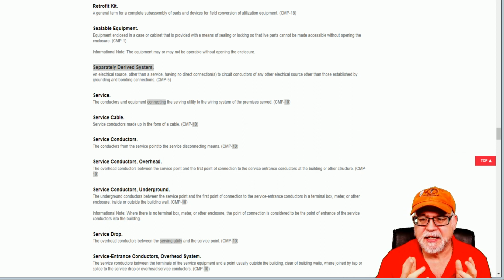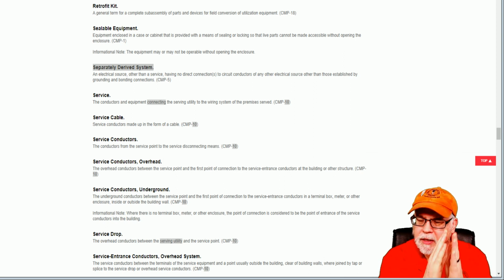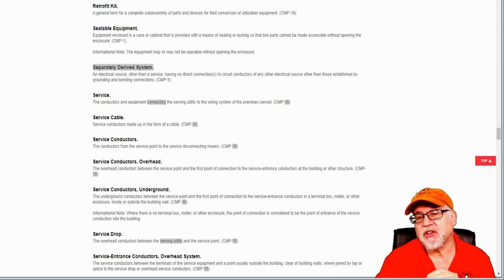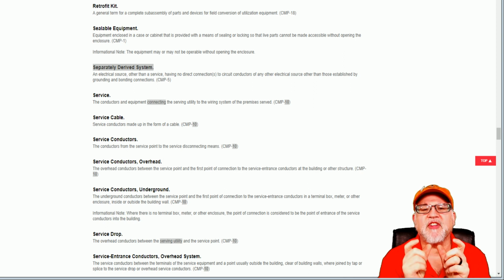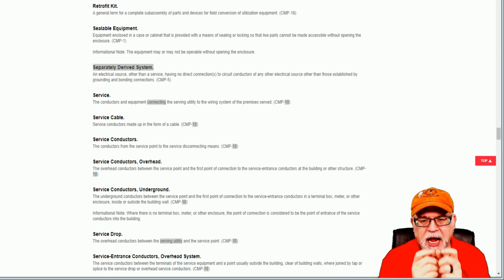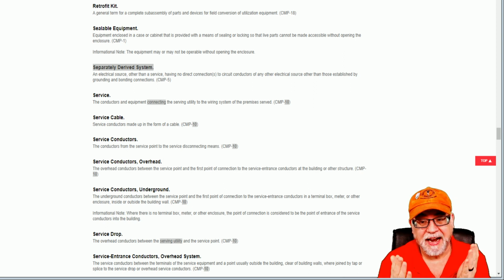Now, we still have bonding. We still have all those requirements that will be intimate. We're talking about the ungrounded and grounding components. Now, if I have a transfer switch, which is typically what you're going to see in residential, you have a solidly connected grounded terminal bus. So the grounded conductor from your generator and from your utility commonly connect on one common bus. So they are in direct contact. So they are not separately derived systems.